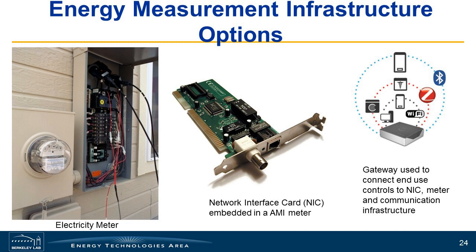You have several options for the electricity meter. It can be an AMI meter. It can be a high-resolution AMI meter, which would be tracking data at 5-minute intervals or less. There's power quality meters, which are an advanced 3-phase meter.